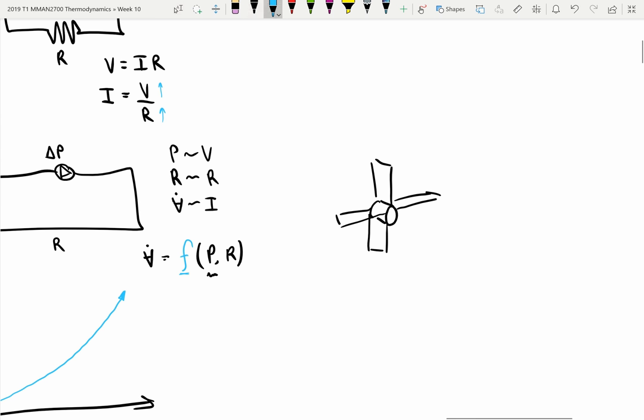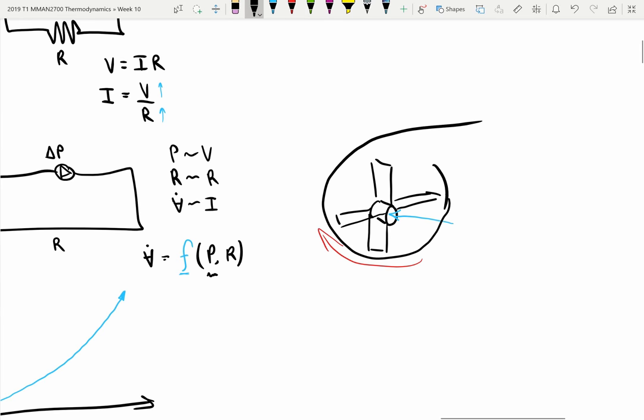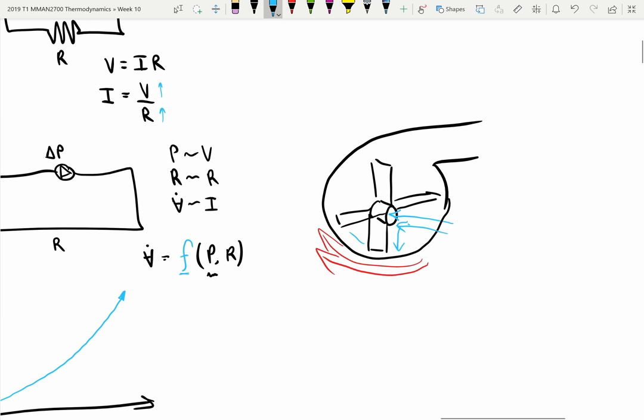The water is going to flow into the centre. These vanes are going to turn around, and there is a casing or a scroll around the outside. As these vanes turn around — they're forced by a motor to turn around — the water is drawn in near the hub. As these turn, it's forced to the outside by centrifugal force, swept along the outside of the scroll, and when it gets to the top it goes out the outlet pipe.